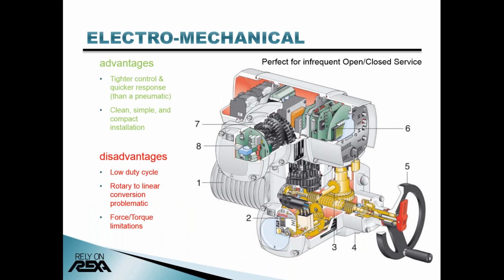Next is electromechanical actuation, most commonly found in on-off type service, which provides tighter control and better frequency response than a pneumatic actuator. However, electromechanical actuators can have limited duty cycle, usually around 25 to 30%, limited force or torque output, and very few fail-safe options available. In addition, the mechanisms involved for rotary to linear conversion are troublesome, especially in high thrust applications.